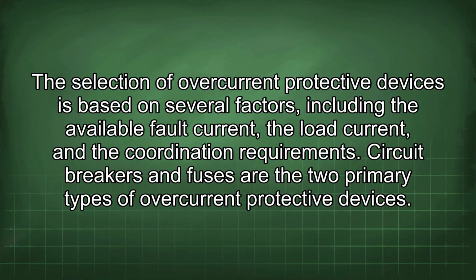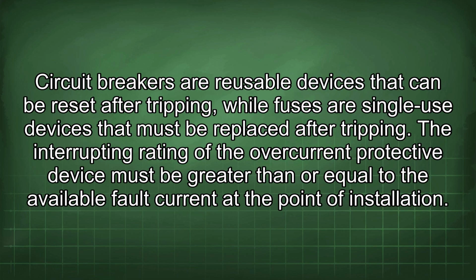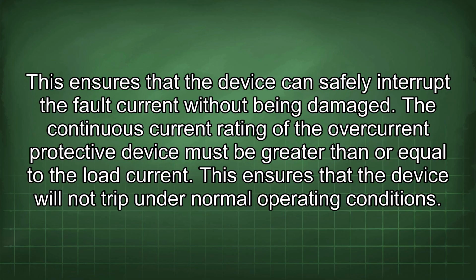The selection of overcurrent protective devices is based on several factors, including the available fault current, the load current, and the coordination requirements. Circuit breakers and fuses are the two primary types of overcurrent protective devices. Circuit breakers are reusable devices that can be reset after tripping, while fuses are single-use devices that must be replaced after tripping. The interrupting rating of the overcurrent protective device must be greater than or equal to the available fault current at the point of installation. This ensures that the device can safely interrupt the fault current without being damaged.